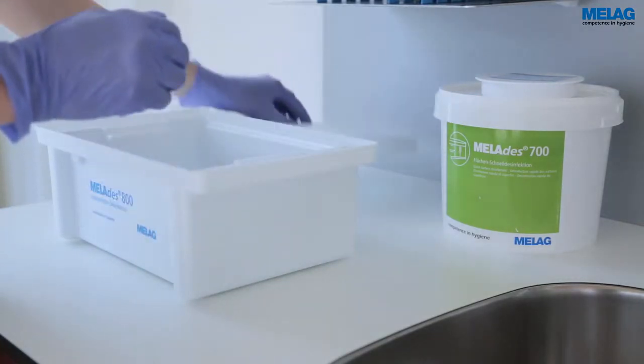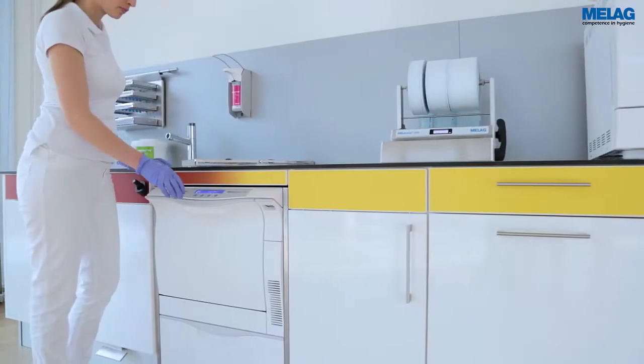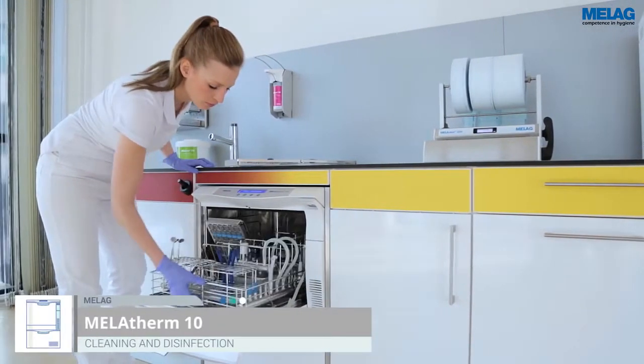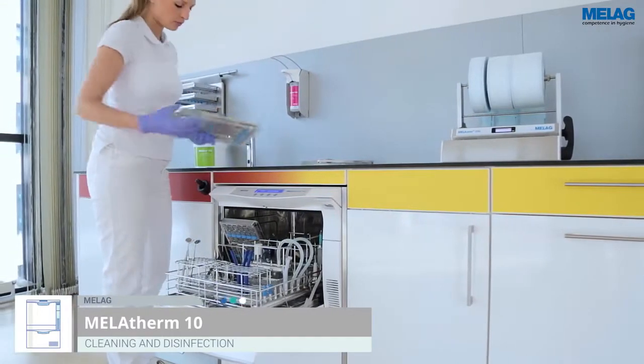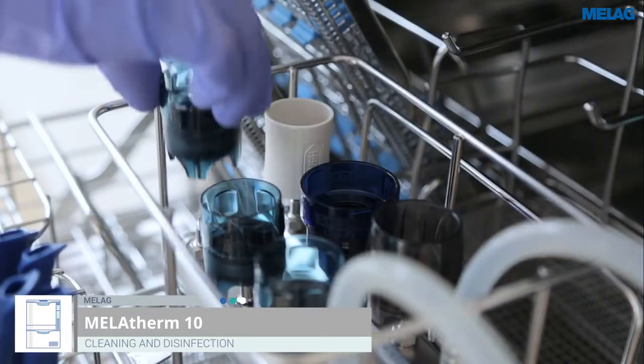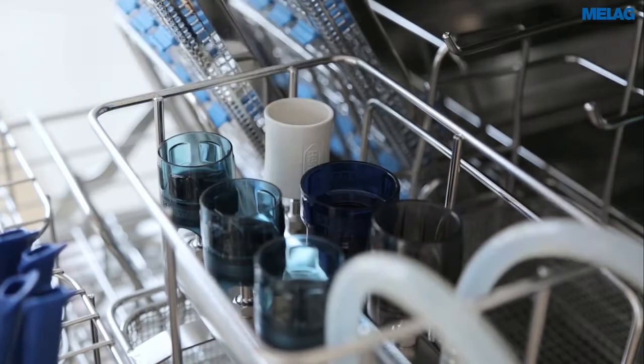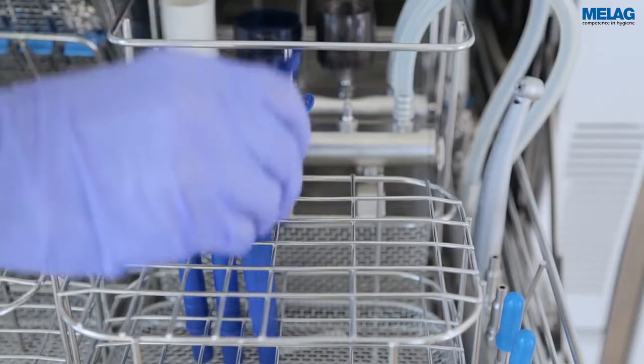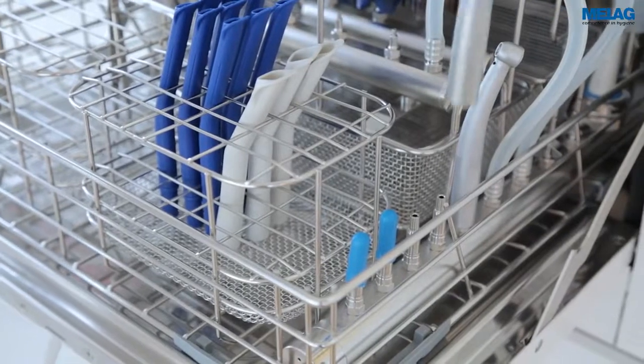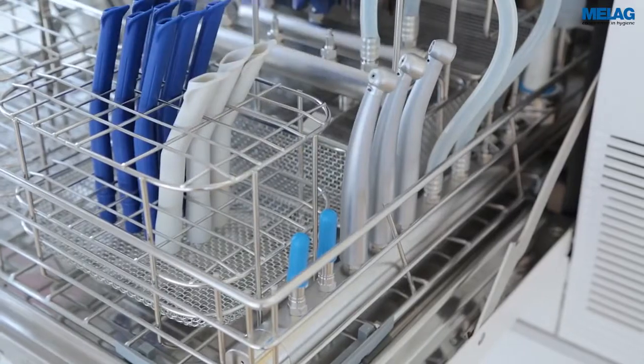We recommend pre-cleaning to remove hardly soluble dental materials before the cleaning and disinfection process in the MELAtherm 10 washer disinfector. With over 80 specially adapted types of insert baskets and further accessories, the practice-optimised washing chamber of the MELAtherm 10 can be adapted to the individual user's needs. An ever greater importance in the treatment process is placed on standardised decontamination of hollow instruments.